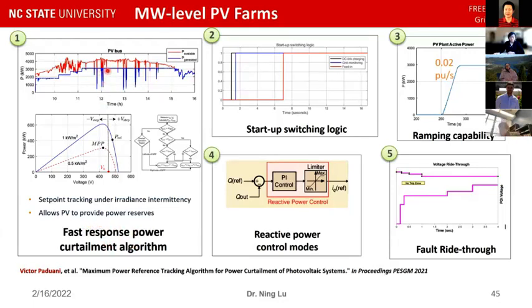The reason we developed that is we found that a lot of our microgrid control functions require us to control not only the BAS system and the battery system, but also the PV, because we have very limited capability there. If we use the battery only, sometimes we have to shut down the whole system because the PV does not have any capability to regulate its real power. So we developed this fast response PV curtailment method so that the PV can follow a power reference. We also modeled the startup switching logic, reactive control modes, ramping capability, and the fault ride-through.